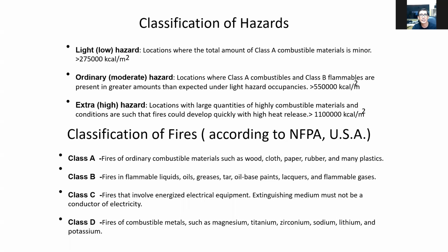So the classification of fires according to NFPA USA, we have Class A, Class B, Class C, and Class D. Class A fires are fires of ordinary combustible materials such as wood, cloth, paper, rubber, and many plastics. Class B fires are fires in flammable liquids like oil, grease, tar, oil-based paint, lacquer, and flammable gases. Class C fires involve energized electrical equipment. The extinguishing medium must not be a conductor of electricity. And Class D fires are fires of combustible metals such as magnesium, titanium, zirconium, sodium, lithium, and potassium. So these are the different classifications of fires according to the composition or property of the material. So we have classification of fires according to hazards, and we have classification of fires according to materials.